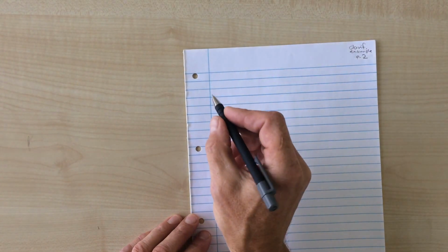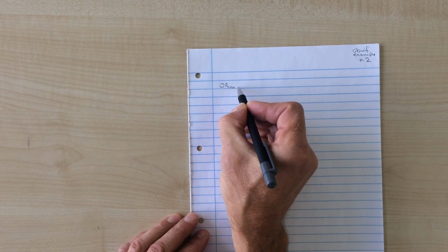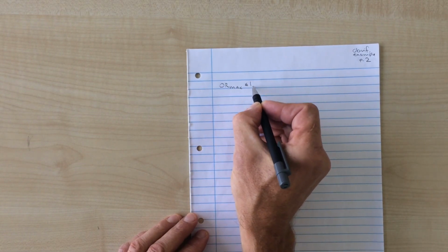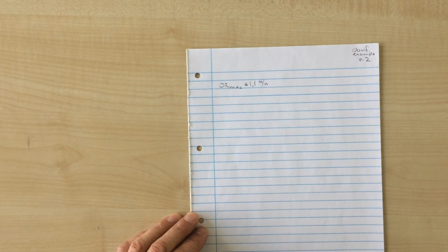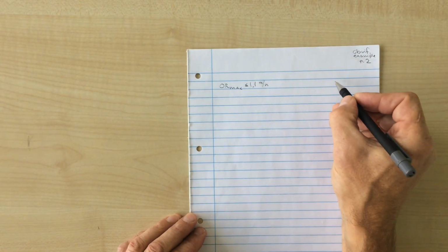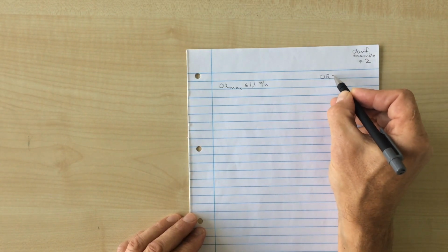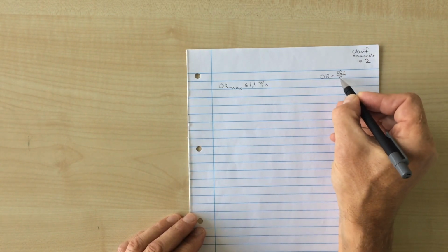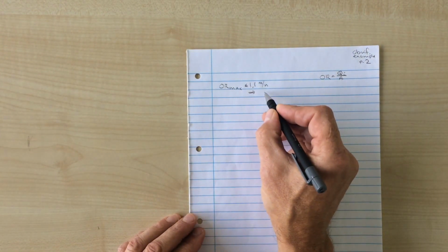The first area will be respecting the overflow rate maximum of less than 1.1 meter per hour, so that's in the storm situation. Since the overflow rate is defined, as I wrote before, as the inlet flow divided by the area, I can calculate the necessary area to fulfill this criteria.